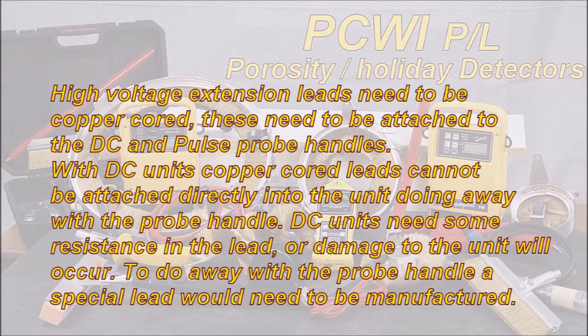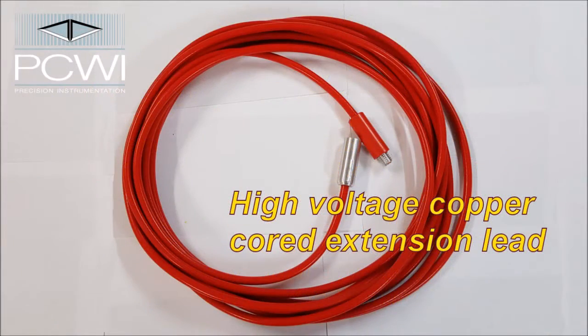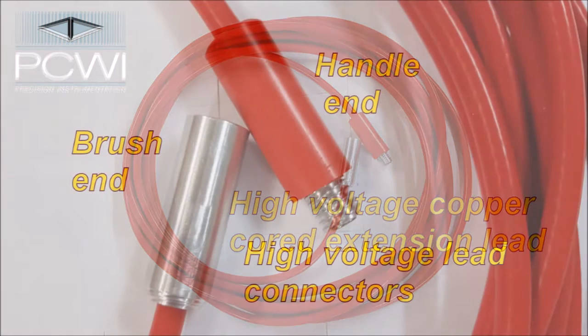High voltage extension leads need to be copper cored. These need to be attached to the DC and pulse probe handles. With DC units, copper cored leads cannot be attached directly to the unit, doing away with the probe handle. DC units need some resistance in the lead, or damage to the unit will occur. To do away with the probe handle, a special lead would need to be manufactured — please contact us.